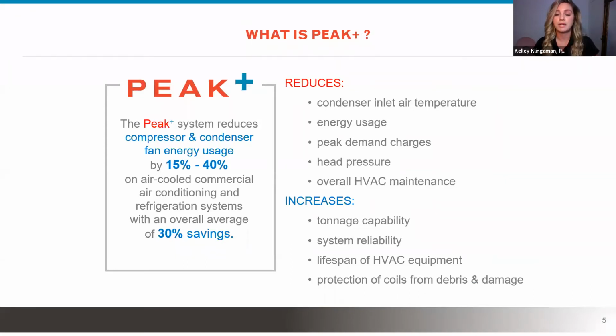We're also reducing head pressure. So with our system in place, your unit is never going to experience those peak conditions. It's never going to experience a 95-degree day with our system spraying. So that head pressure, you'll not have issues with high head pressure anymore with our system spraying. We're reducing the overall HVAC maintenance. So like I said, with head pressure reduction, your unit is just not working as hard. It's going to last longer, and you're not going to have as many issues with compressors going out or frequent coil cleanings and things like that.